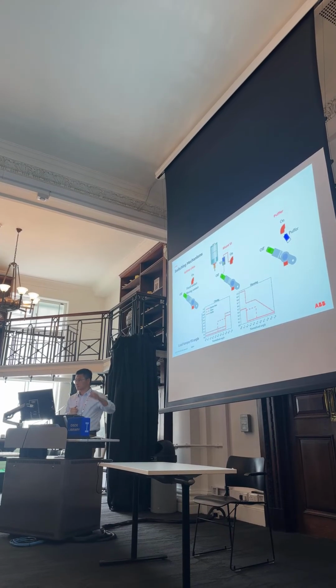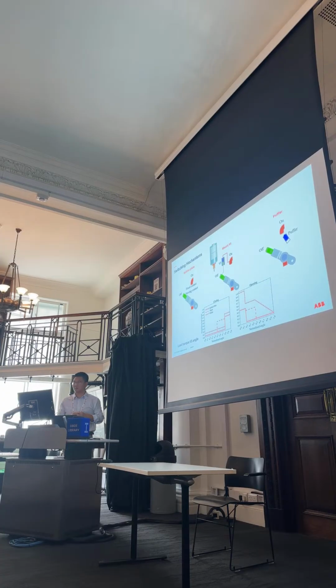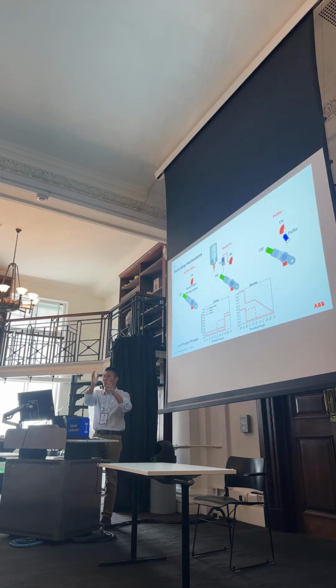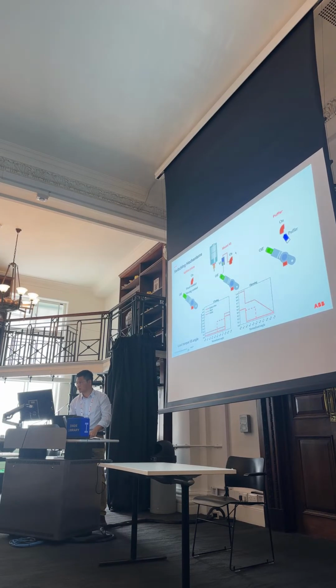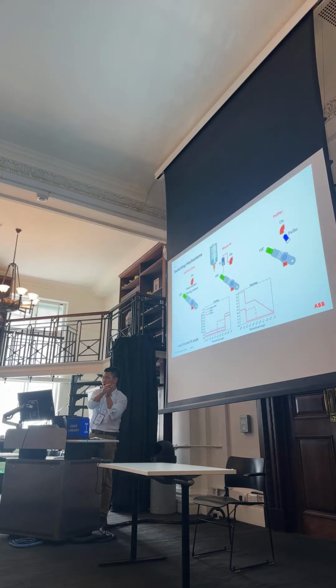Maybe just a side note for you, how does this mechanism work? For both connecting and opening, the current first goes through the vacuum interrupter, and then to the fixed contact. Imagine the current comes from here, for example, it goes first through the vacuum interrupter, and then to the moving contact. The separation of moving contact and fixed contact now happens inside the vacuum interrupter. Since it is a vacuum, it will not generate an arc. That's the fancy thing here, why we use this vacuum interrupter.